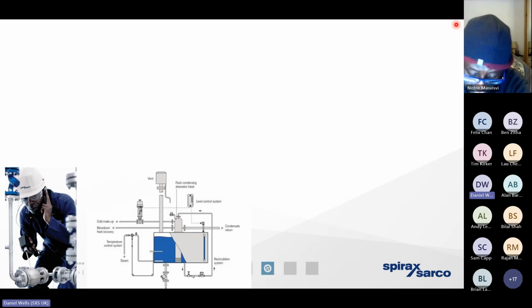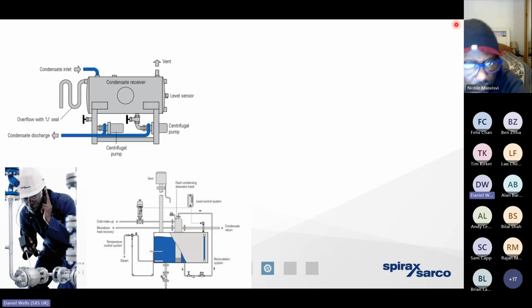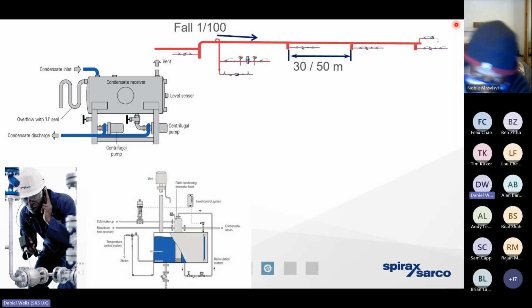The reason being, well, we want to get as much of that hot condensate back to the boiler house as we possibly can. Remembering from the steam tables, the hotter the water going into the boiler, the less gas we need to burn. So ensuring that we've got the correct, well-designed condensate return infrastructure. We want to keep the steam as dry as we possibly can. Remember, the drier the steam, the more energy there is present within the steam. So we need to engineer the infrastructure correctly to allow that condensate to drain away across the trap.